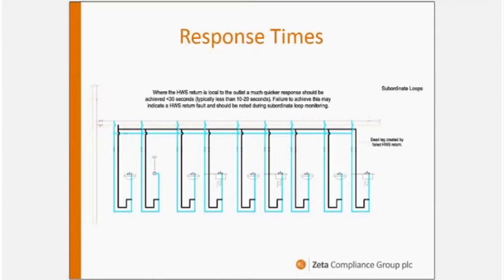The other thing is, if you can't get at those loops, what you'll sometimes find is that you get a clue. You run the tap, and we'll stand there for 60 seconds and take the hot water temperature. What we should find if the loop is flowing is that it responds very, very much more quickly, because it should only be coming a short distance from the flow leg. If it's taking more than about 20-30 seconds, there's a good indication that that loop is not flowing. And again, we've now got a substantial dead leg on the system, which otherwise would have been invisible, would have been unknown.